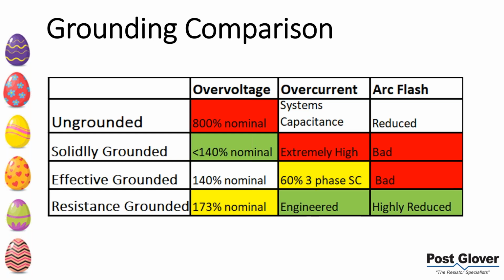For resistance grounded, the voltage is usually not an issue for other applications. It's not as much of an issue. You still have to worry about some pieces of equipment for low voltage, not wire, but more like surge suppressors and stuff like that: how you hook them up, what they're rated for. I mean, voltage is going to be different. But that's where you want to worry about it, for wind and solar. You're going to worry about that voltage there. Your overcurrent is not an issue. It's engineered, so if you engineer it correctly, you should not have much issue with that. So if you want it to be 10 amps, it's 10 amps. That's my point there. Then arc flash, I've already mentioned that it's highly reduced.